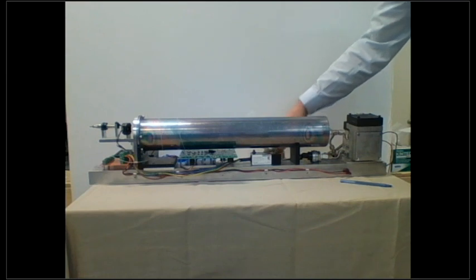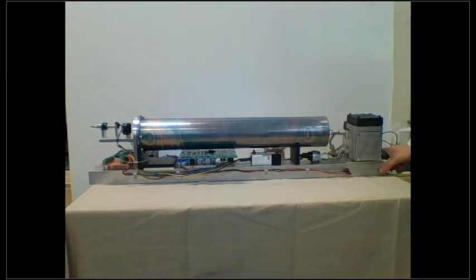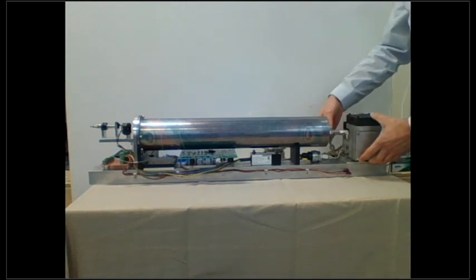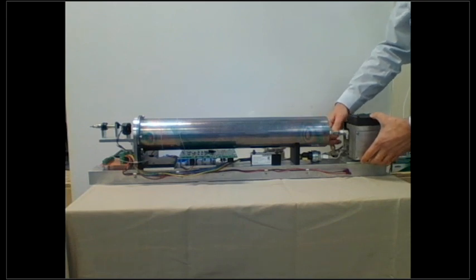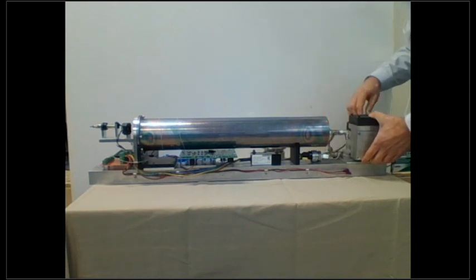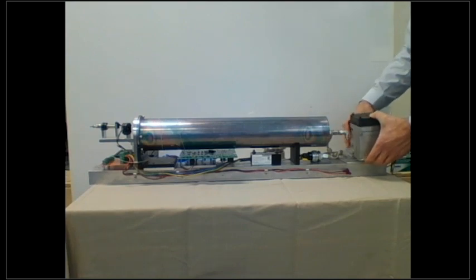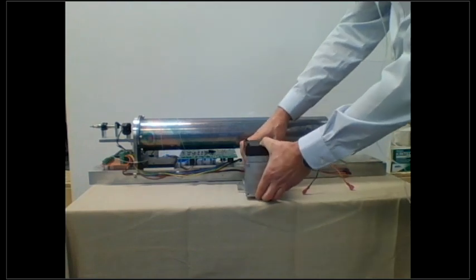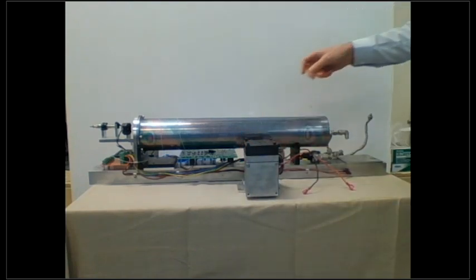Now we talked about some annual maintenance requirements for the vacuum pump. So the vacuum pump is here. I will mention that it's not necessary to take the whole rail out if you want to work on the vacuum pump. You can simply slide it out of the explosion-proof enclosure just far enough to give you access to the pump. I'm actually going to take it off the rail here just to give you a closer look at it. So you undo a few fittings here, and it gives you access to the pump.